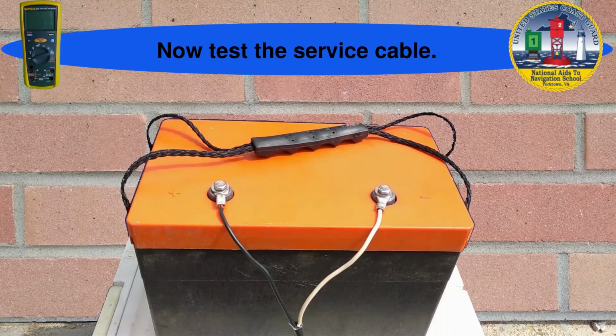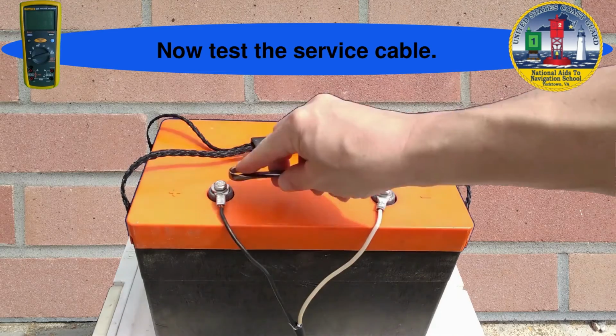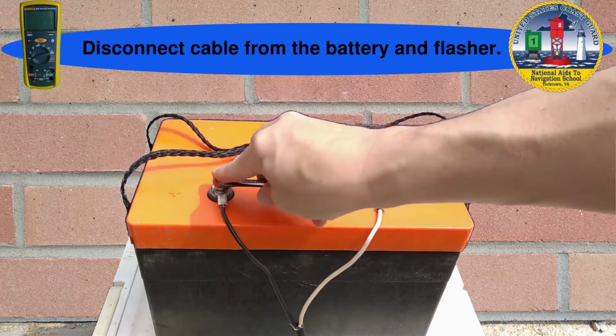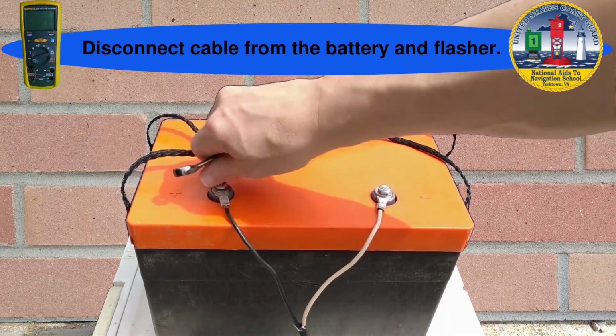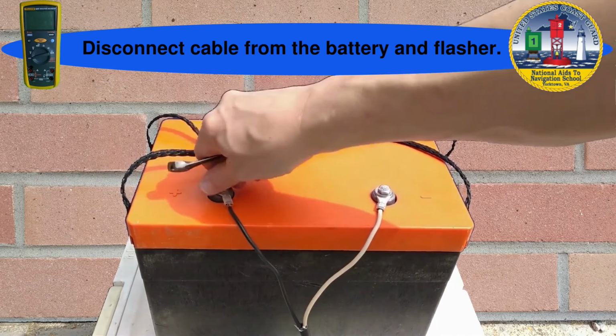It is important to isolate the cable under test by disconnecting it from its power source and aid. Remember to use caution and not touch any of the conductive parts when taking readings, as the meter is capable of producing high voltages.